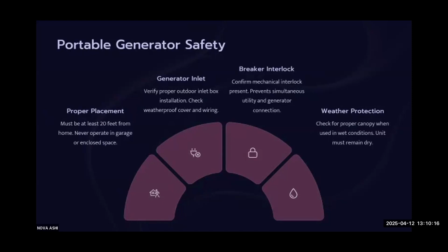Let me show you, this right here is the breaker interlock. Basically, if you have generator power feeding back into the house, you can't power up the panel, the breaker is forced into the off position. So unless you turn off the utility breaker, that's the only way to power your house. It interlocks with the main breaker, usually one of the top two breakers, either left or right, and it installs very easily.